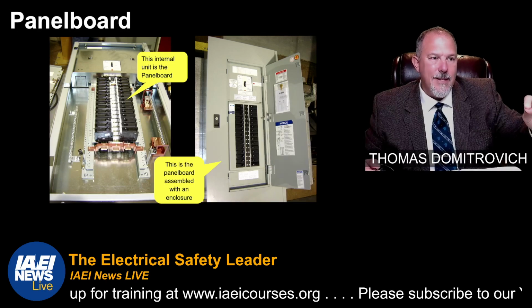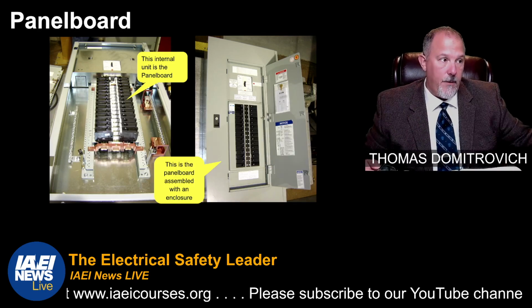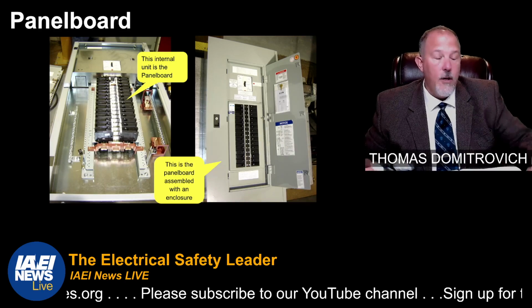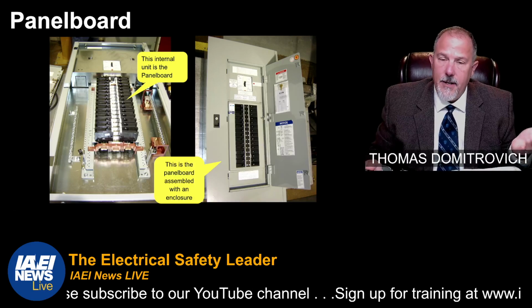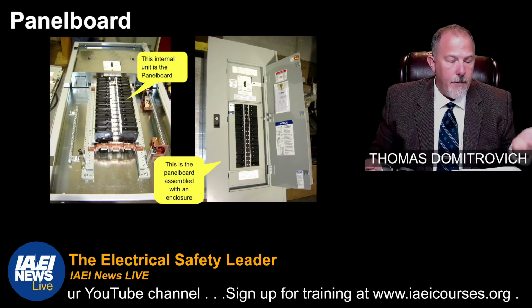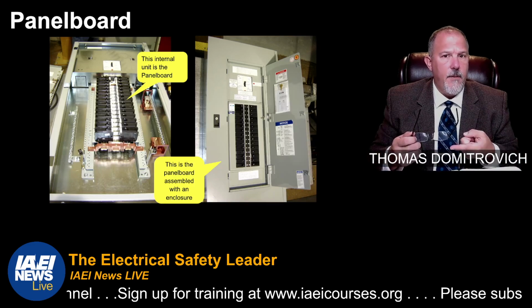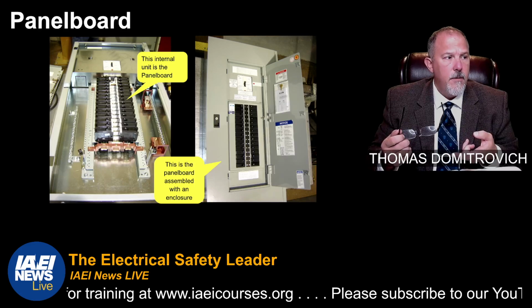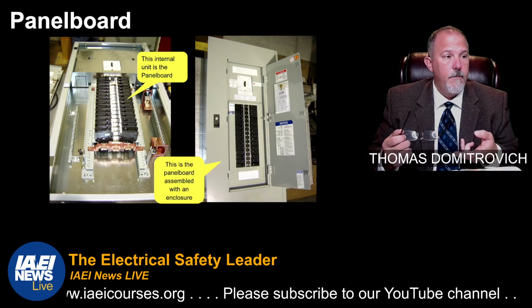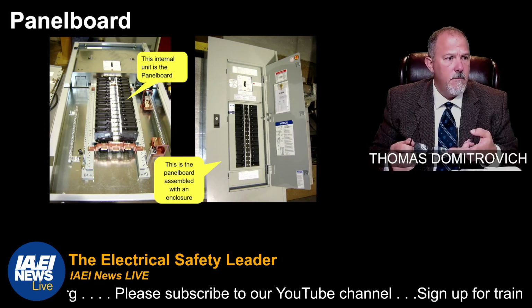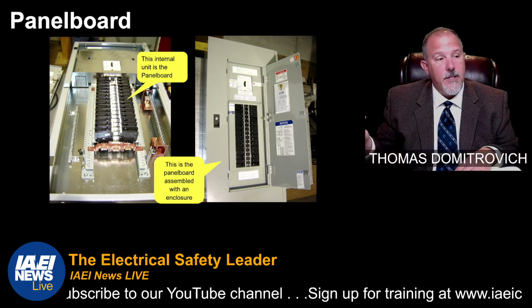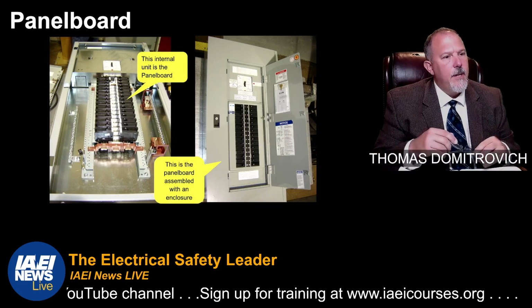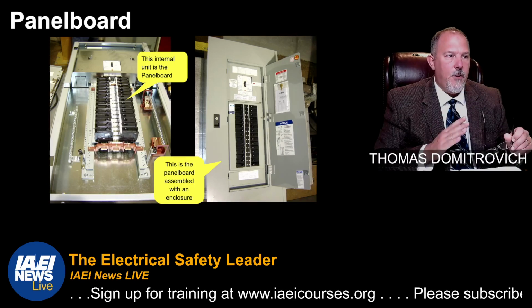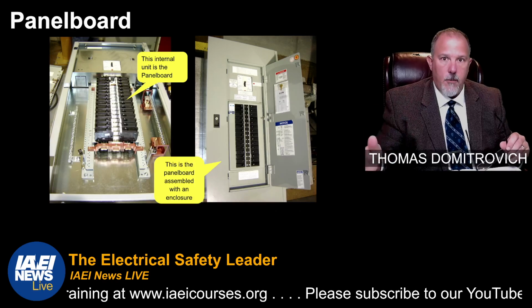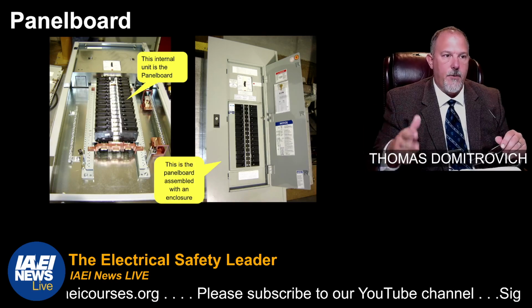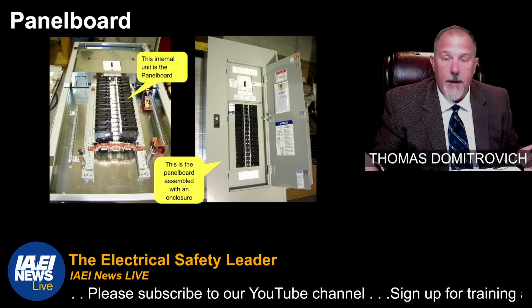So if the fault current is less than 10,000, then I don't have to evaluate the panel board and enclosure combination for the application. What does that mean? That's pretty generic. Does that mean I don't have to consider the environmental conditions? Does that mean I don't have to think about HAZLOC? I don't know. In any case, HAZLOC's back there. But anyhow, I would say that should not. I believe all they're talking about is evaluated for short circuit current rating for the application, because all panel boards are going to be apparently greater than 10,000 amps short circuit current rating.